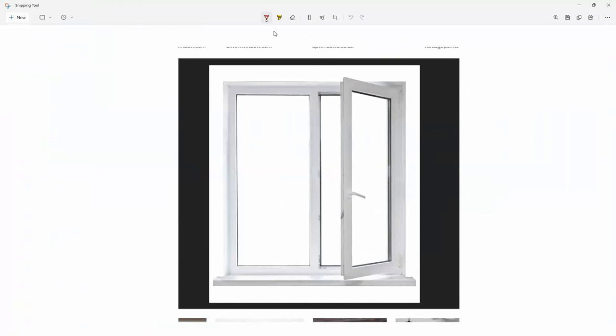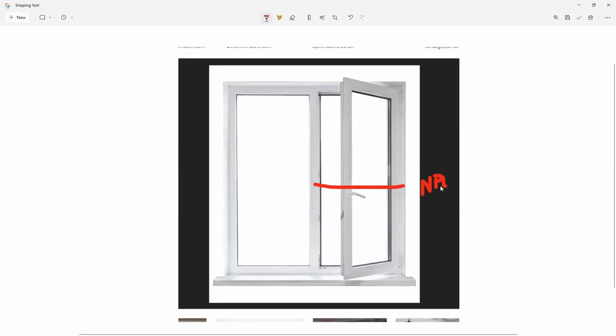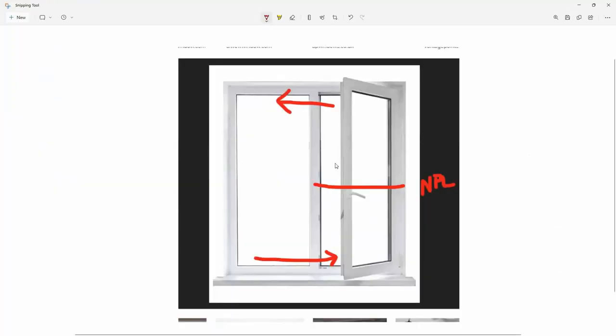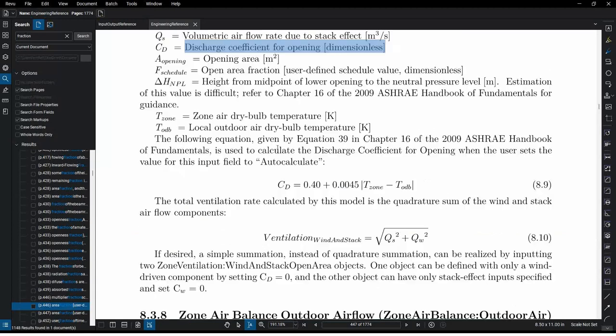The stack effect models what happens when you open a window: there is a neutral pressure level somewhere in the middle of the window. Air is sucked in at the bottom portion and discharged out the top portion. The measure combines the stack effect and the wind effect as a quadrature sum to calculate a ventilation value for that room.